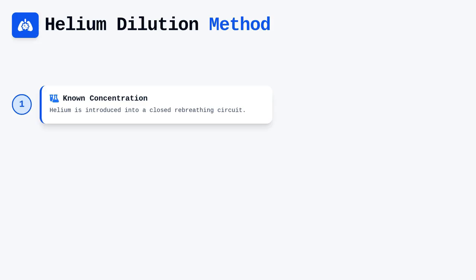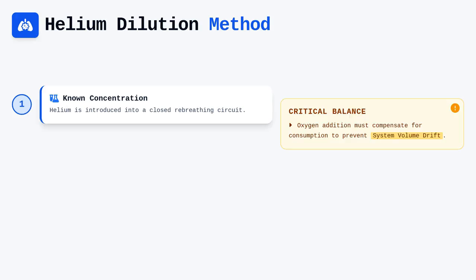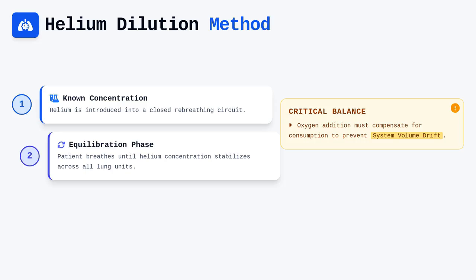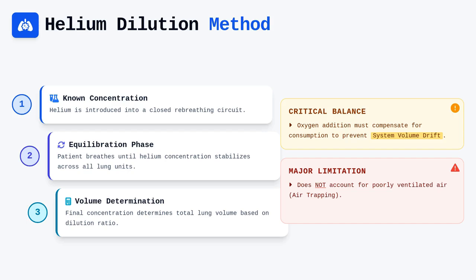Helium dilution is a closed-circuit method that utilizes the principle of gas concentration equilibrium to determine lung volume. We put a known concentration of helium into a rebreathing circuit, and as the patient breathes, the helium becomes diluted by the air already inside the lungs. We must carefully manage the oxygen addition lines during the equilibration phase to keep the system volume constant and compensate for the oxygen consumed by the patient. If the oxygen addition is not balanced correctly, the system volume drifts, rendering the final calculation unreliable.